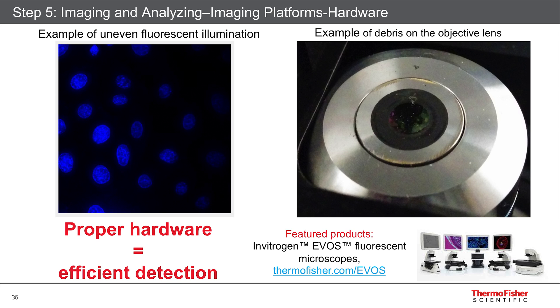Here are some examples of hardware that has not been optimized. On the left is an image of DAPI-labeled nuclei — you can see they're dimmer in the upper right compared to the lower left. That's because this was taken on a traditional microscope where the mercury bulb was not aligned properly. No matter where you move the sample on the stage, that area will always be dimmer, requiring realignment. To the right is an image of an objective lens that hasn't been properly cleaned — you can see dust and debris, which reduces resolution and may cause optical artifacts. Some fibers can also be autofluorescent. There's also visible damage to the objective from being scraped against the stage, so always be careful about that.